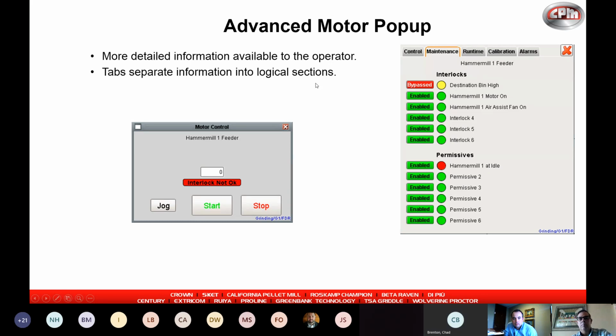So the operator himself can look at this and say, hey, this is why I can't start this motor—the hammer mill isn't at idle yet, we need to wait for it to come down in amps before starting again. Or the motor isn't even on, or the air assist fan isn't on. These would be customized for every motor, so when you click on that motor, you'd know exactly what's happening with it.